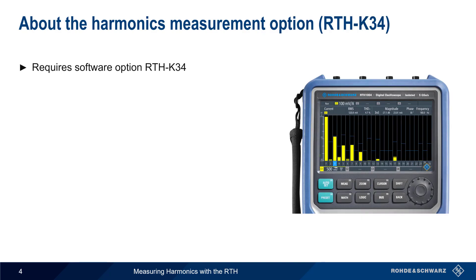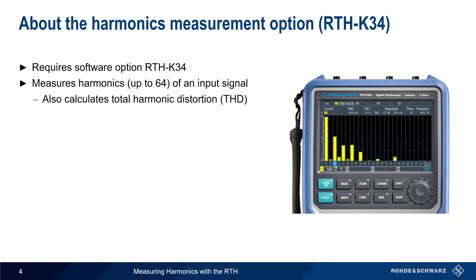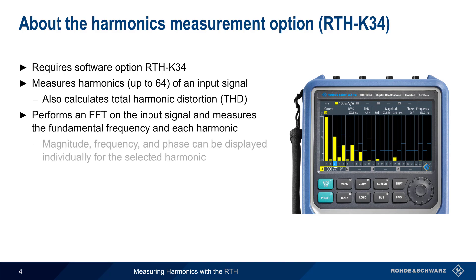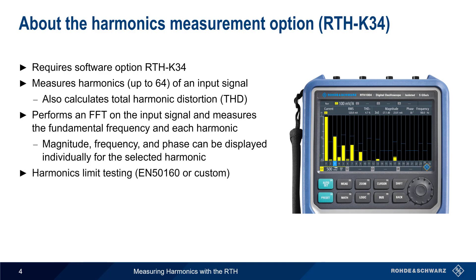Measuring harmonics with the RTH requires software option RTH-K34. This option enables measurements of the first 64 harmonics of the input signal, and also calculates the total harmonic distortion. The RTH does this by performing an FFT, or Fast Fourier Transform, on the input signal, and then measuring the fundamental frequency component and each harmonic. The magnitude, frequency, and phase of each harmonic can be displayed individually. This option also supports harmonic limit testing, either using the standard EN50160 values or a user-defined set of limits.